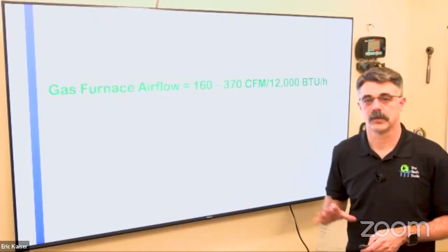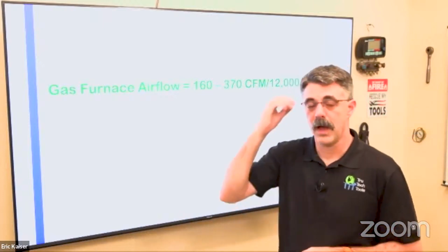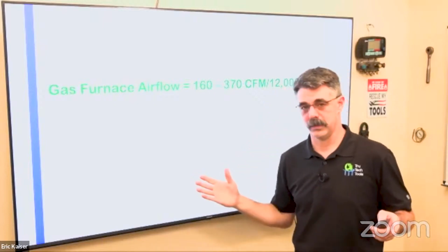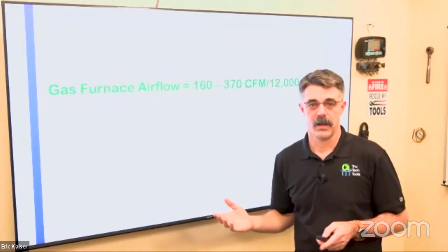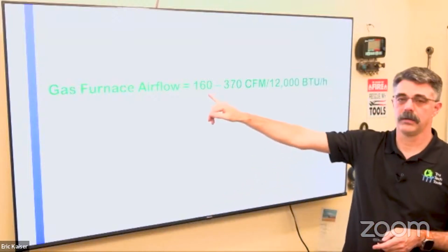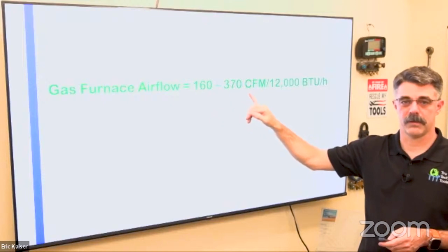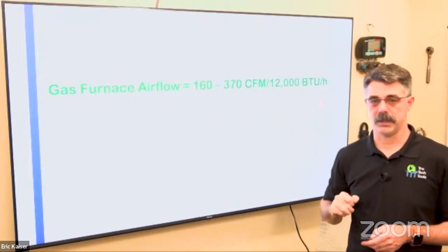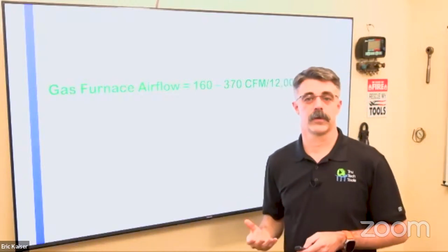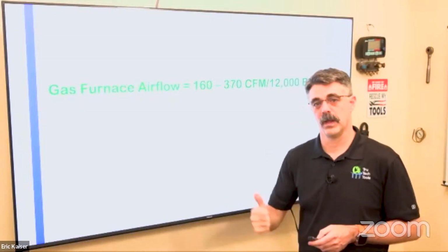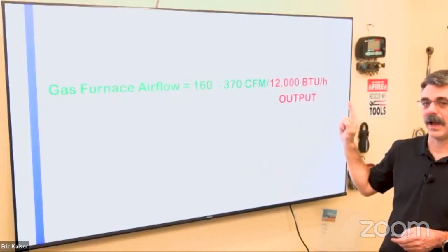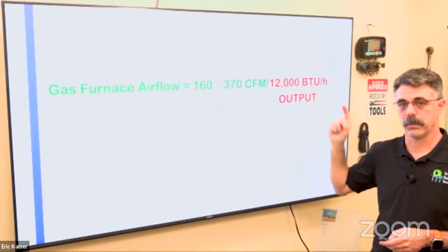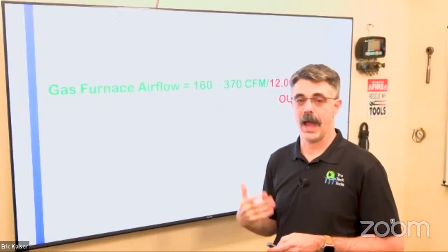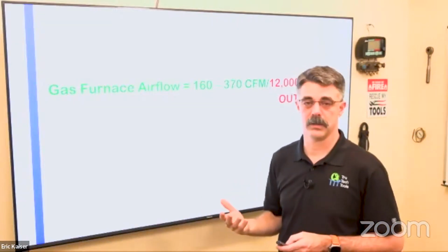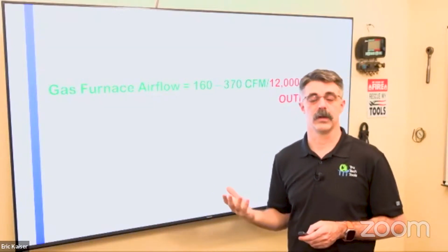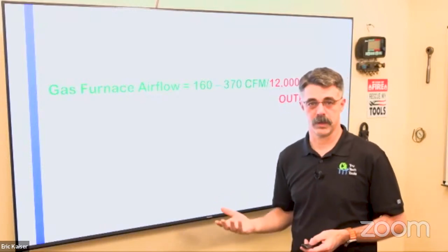Now, let's talk a little bit more about airflow in different units. A gas furnace, because there's different efficiencies, things like that, is going to run anywhere from 160 to 370 CFM per 12,000 BTUs. Now, as we know, gas furnaces are typically rated on input BTUs. This value, however, is output BTUs. So per 12,000 BTUs of output, which happens to correlate to a ton of air conditioning, which we know nominal airflow for an air conditioner is between 350 and 450 per ton.